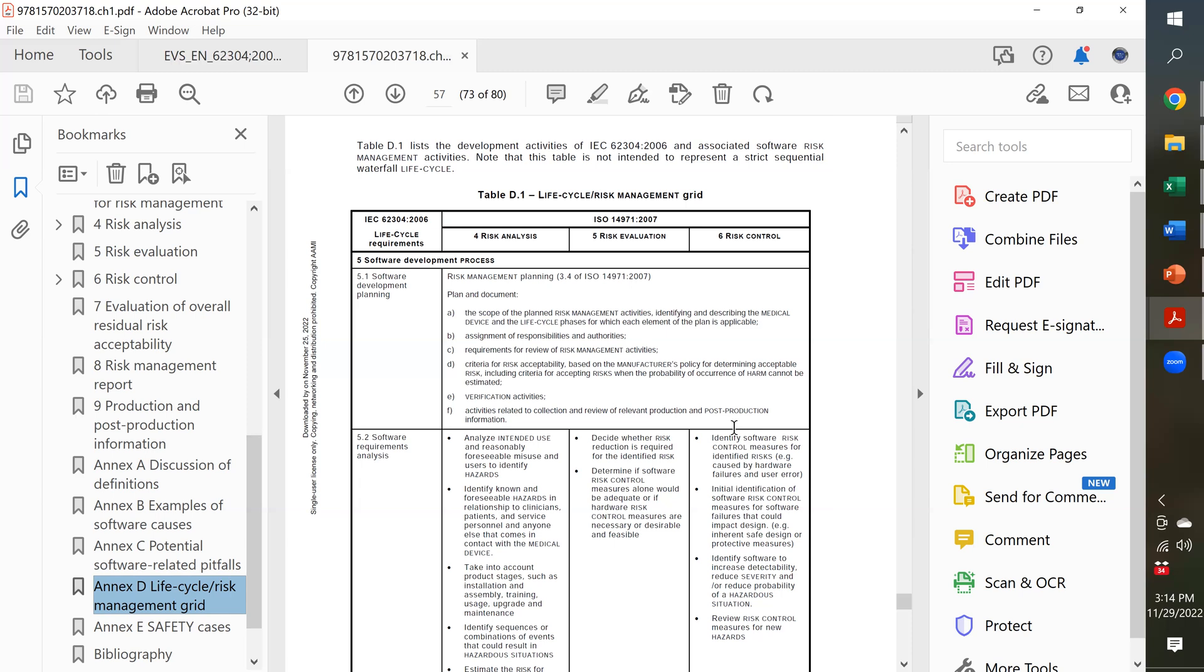do your hazard analysis and make sure each of those hazards has a risk control that's identified as a software requirement specification, and you flush out how that software risk control is going to be implemented in your SDS, your software design specification.